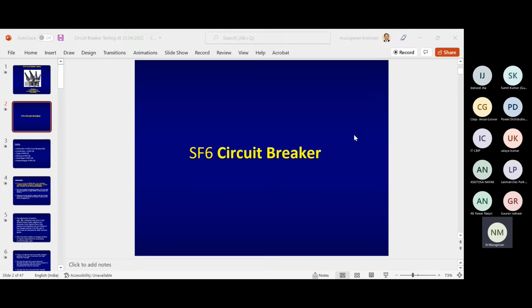So can you tell me what are the different kinds of circuit breaker available? Air circuit breaker, vacuum circuit breaker, air blast circuit breaker, SF6 circuit breaker, molded case circuit breaker, MCB, RCCB, ELCB. Wonderful, very nice. You have covered both LT, low tension, as well as high voltage. MCB, MCCB all come under low voltage circuit breakers, the LT side.